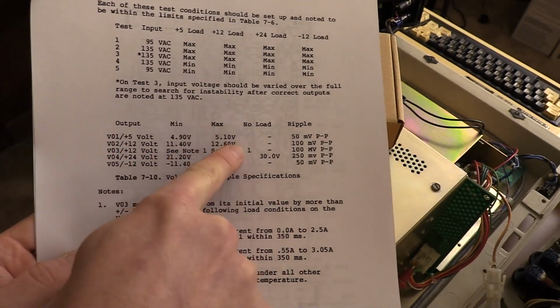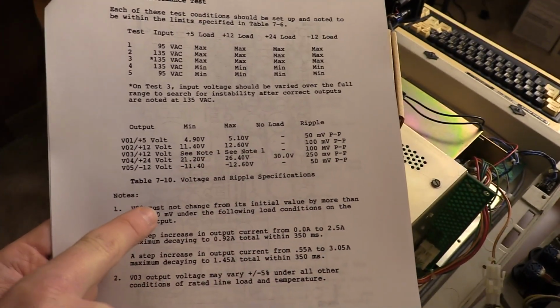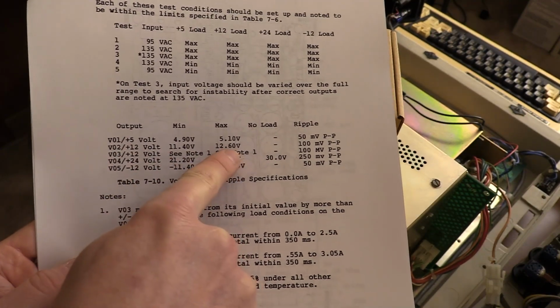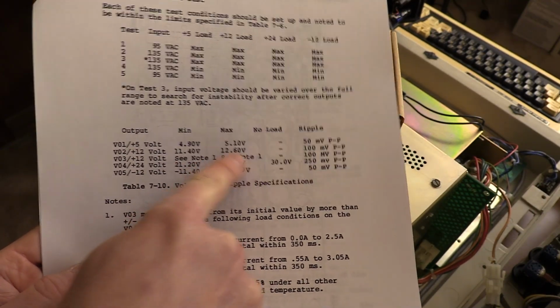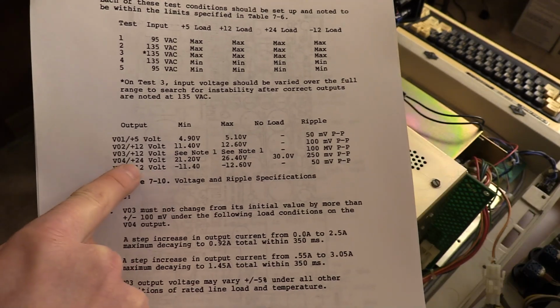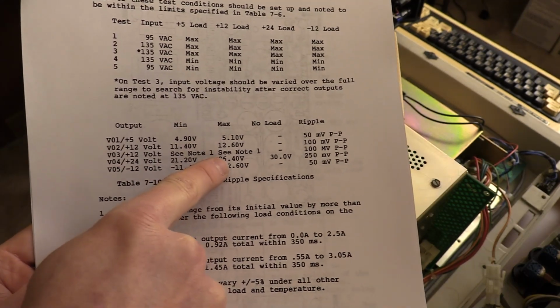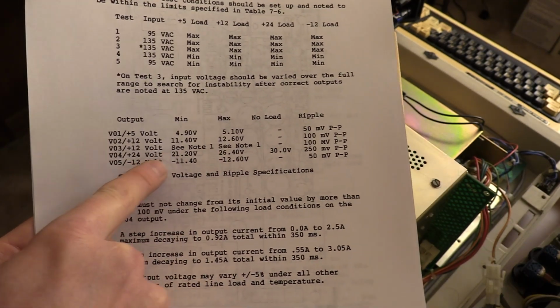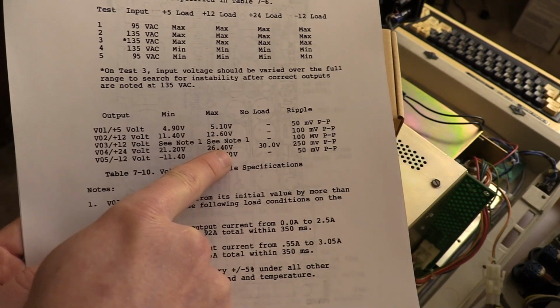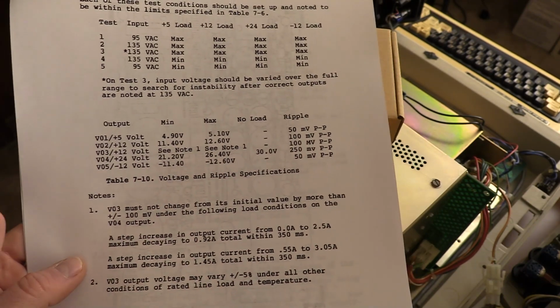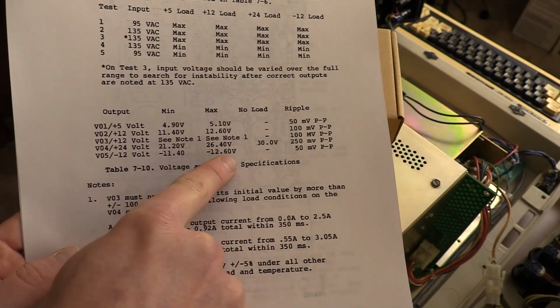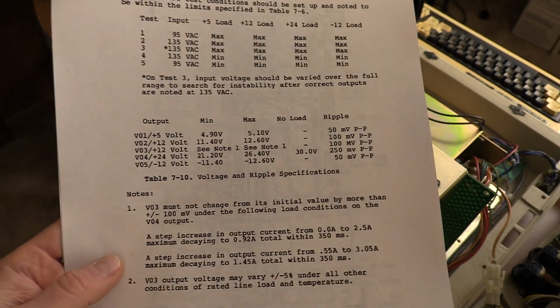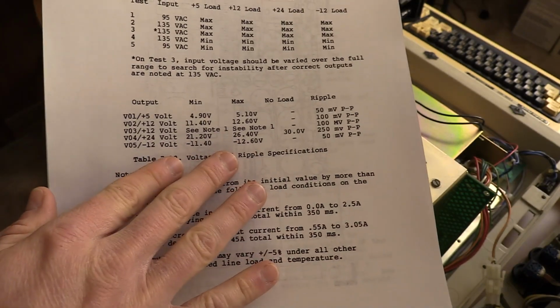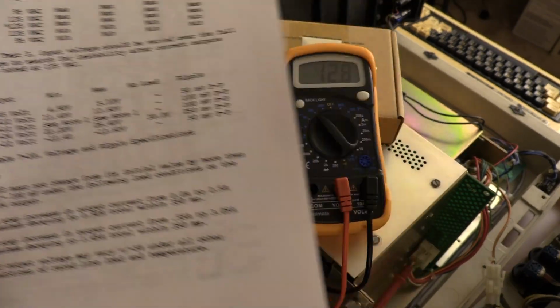And by check it out, I mean here it is: 4.9 to 5.1 on the 5 volt rail, so we are good there. 11.4 to 12.6 on the plus 12 rail, so we're over there. There's actually another 12 volt rail, so we're going to check both, make sure I find both. 21 to 26 volts on the 24 volt rail, that was dead on. Minus 12 should be minus 11 to minus 12.6, and that was 12.2 or 3, so that's dead on. So the only one that's out of spec is the plus 12 volt rail.